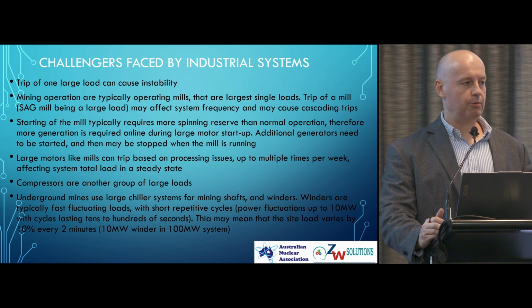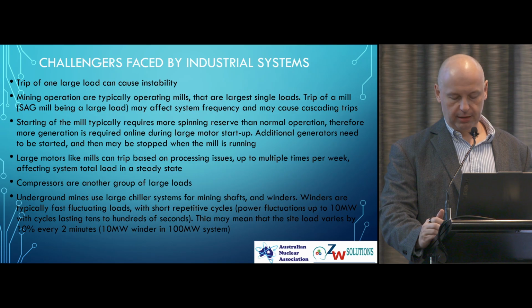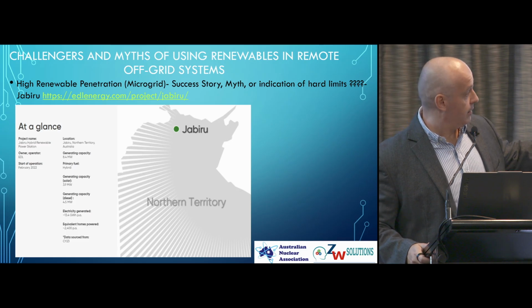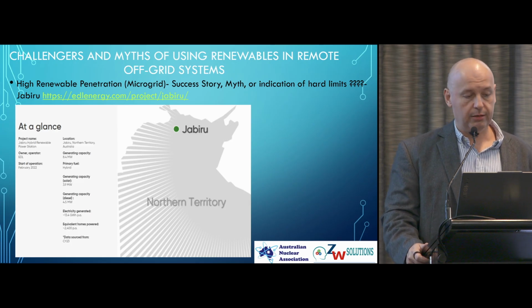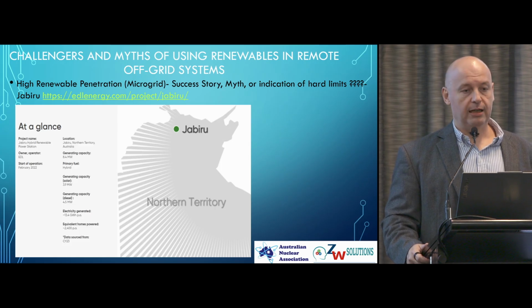It will be somewhat related to the large systems, but it will also show that even in a small system, large renewable penetration is not that viable. That's an easily accessible site in Northern Territory. The load of it is a peak of 2 megawatts, with an average daily load of 1.5 megawatts. 4.5 megawatts of engine generators, 5 units, so 3 times the average load.